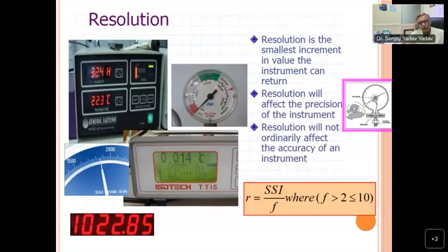So this formula you can use: R = SSI / F. R, SSI is what? Smallest scale interval. So smallest scale interval, and F is the frequency, and frequency is normally dependent upon the user. If you are a perfect user, you can divide it between 2 to 10, but normally it is safer if you divide the smallest scale interval by 2, but there is no restriction. The standard says you can divide it by 10 also if you are an expert and you can resolve the resolution. So that is a clear thing.